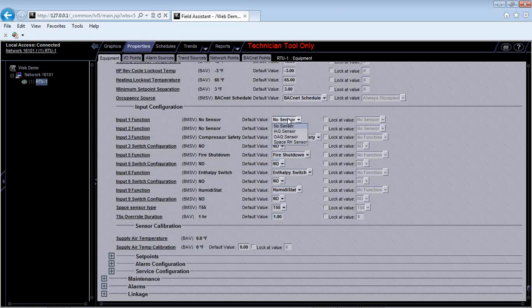Each of those sensors can be a 4 to 20 milliamp or a 0 to 10 volt DC input. Okay, and those are your 2 options for inputs 1 and 2. The manual tells you which inputs can take what type of sensors. So 1 and 2 can take 0 to 10 or 4 to 20. 3 through 9 can only take closing contacts, or 24 volts. So if I have a compressor safety, I can put a current transducer to prove that my compressor's on. I can wire that in to input 3, and then I would tell it I have a compressor safety on there. Now, whenever that current transducer reads off when my compressor's on, then I'm going to go into alarm because I know to reference it.